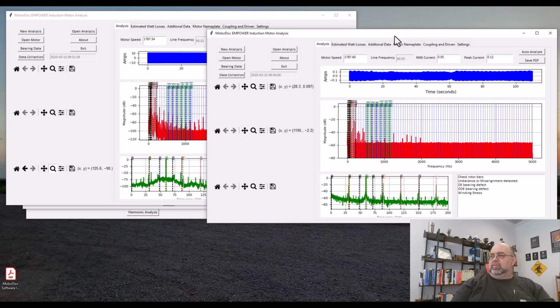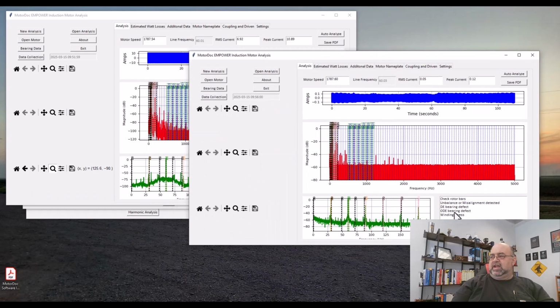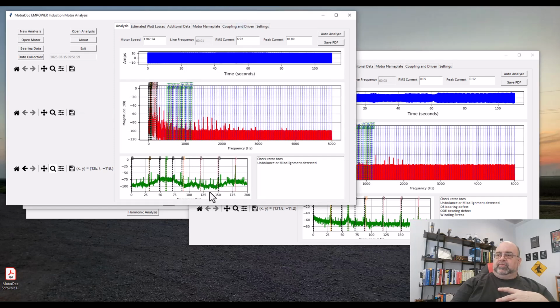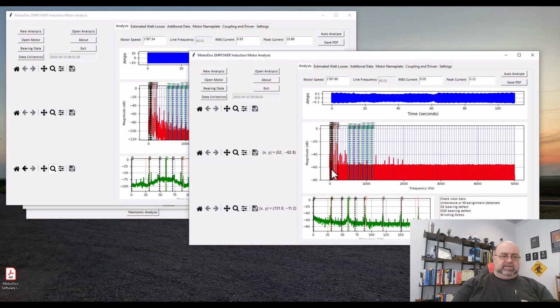My levels are lower, but as you can see, I've got a lot of other things it says it's seeing. Okay, so both bearings bad, all this other stuff. And this is with the adjustment for that raised noise floor. So it thinks it sees a bunch of other stuff going on, and as a matter of fact, there are peaks associated with those, and it's the right speed. So do I actually have a problem? Well, no, those bearings are not showing a significant issue here. They're falling off to one side. So the noise alone from here is doing that. So I've got 1, 2, 3 false positives out of 5 findings. I am aware of this because I have inspected this motor. Okay, so I've got 3 false positives there.